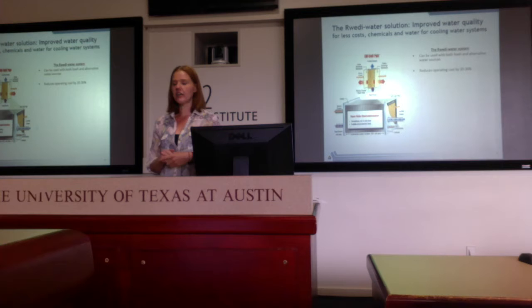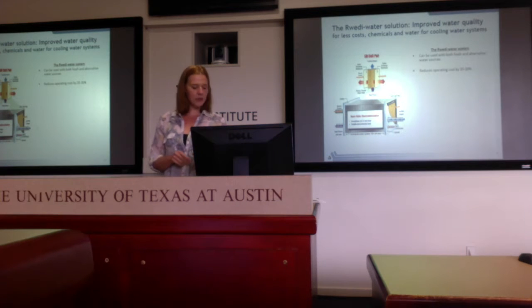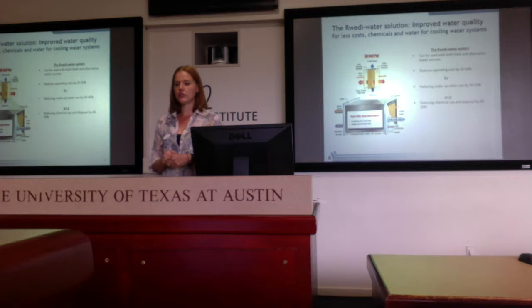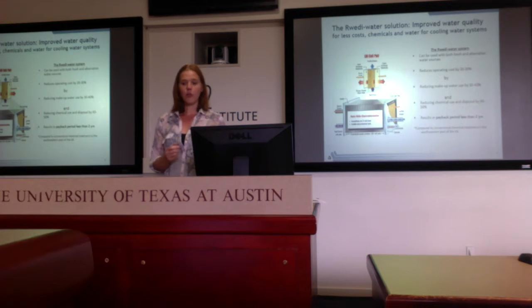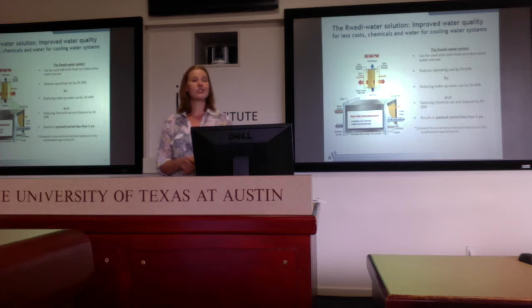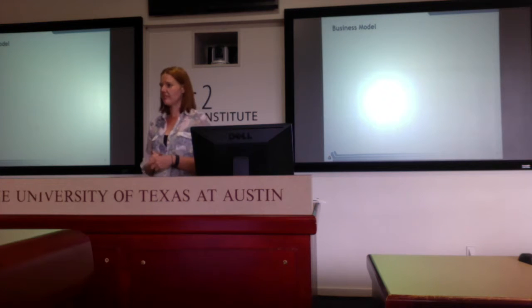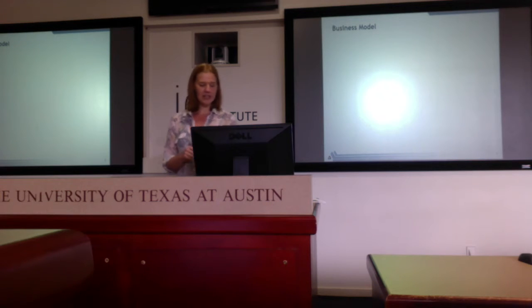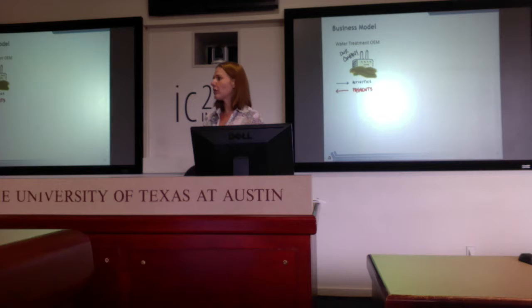This reduces the operating cost by 20 to 30% by allowing you to reduce your makeup water use through increasing your cycles of concentration, and it also allows you to reduce your chemical use and disposal costs by 40 to 50% by improving your water quality to start with. What this means is that you have a payback period of less than 2 years when compared to conventional chemical treatment use. So our business model, we've gone through the Lab-Corps process, which is a DOE program very similar to I-Corps. And we decided through this process that we are going to be a water treatment OEM.